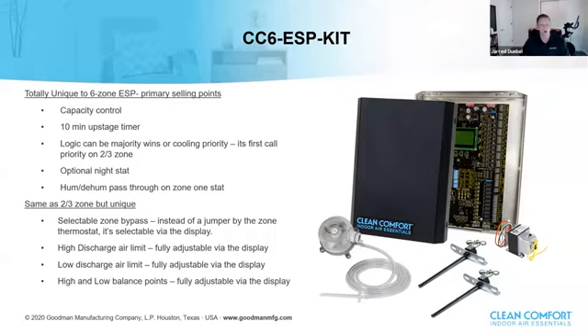On the flip side of that, we have an upstage timer. It's just a simple yes or no. You can turn it on or off through the display. And it's a 10-minute upstage timer, which means if any zone or zones are calling for 10 minutes or more, we'll automatically upstage the equipment. Again, totally optional.